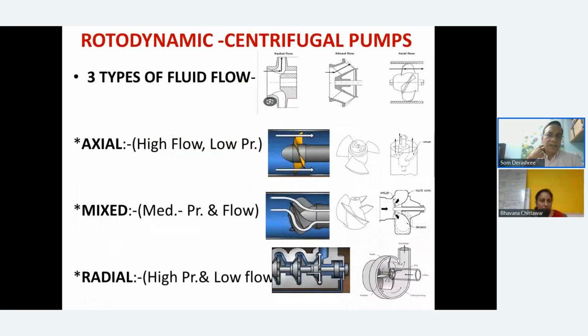Let's have a look at how they look. The axial pumps are simply axial flow. You have vanes pushing the liquid backward on a single shaft, and you have very high flow and very low pressure. That is the main characteristic in irrigation or lift irrigation, where you have those kinds of pumps. Even in the salt works you will find a lot of these pumps, where you don't need much head, but you need a lot of volume. The whole seawater is pumped into the salt farms.